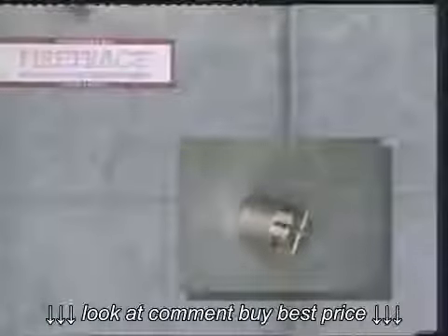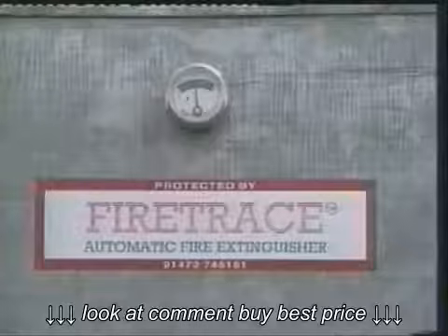Following the success of the FireTrace modular systems, we have developed a similar valve capable of handling the high pressure of CO2 or nitrogen, compatible with a standard trace detection tube. Extinguishant gas is discharged via diffuser nozzles interconnected by high pressure steel tubing. As the trace detection tube is maintained at a low pressure, it can be interfaced with our standard range of alarm and plant shutdown equipment.